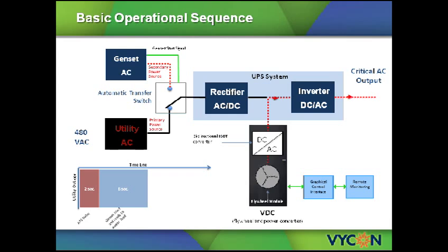As the voltage and frequency from the generator stabilize and are available to the ATS, it will switch from the primary utility source to the generator source and provide the secondary source genset power to the UPS. This ATS switching time typically takes less than 1 second, at which time the UPS rectifier will synchronize to the genset source and start ramping up power onto the genset. Depending on the settings of the UPS, this typically will take less than 2 seconds.